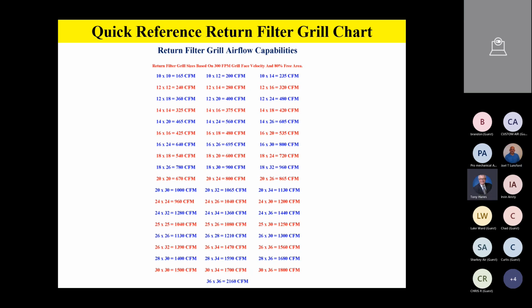And guys, I would add to that, you may want to get on Hart and Cooley's website or Lima, one of the manufacturers of grills, and they will have charts on all of their grills. There's different fin spacing, 1/3 inch, and 1/2 inch and so forth, and commercial grills and what have you. So that's maybe an easier way, to just print out the charts on the grills that you use. Most of what you find out in the field is, I think it was called, 1/3 inch spacing, something like that, and so you can find charts on that.